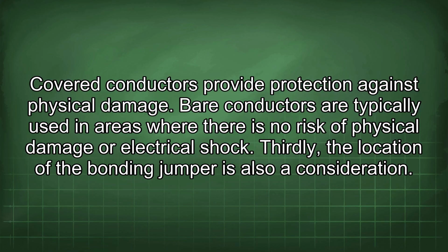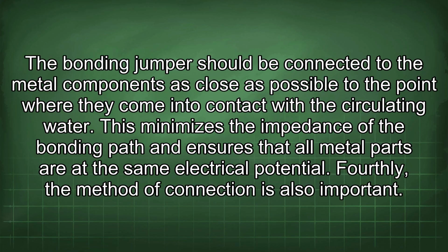Thirdly, the location of the bonding jumper is also a consideration. The bonding jumper should be connected to the metal components as close as possible to the point where they come into contact with the circulating water. This minimizes the impedance of the bonding path and ensures that all metal parts are at the same electrical potential.